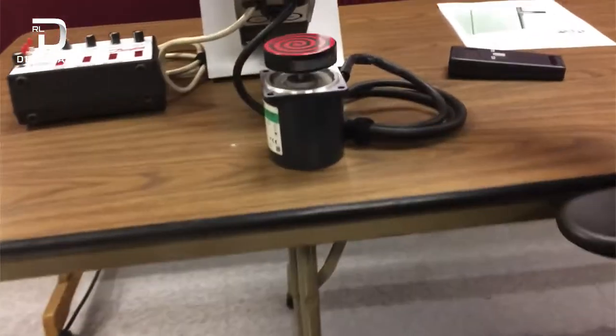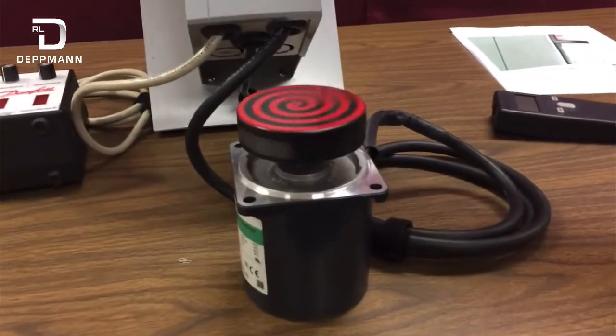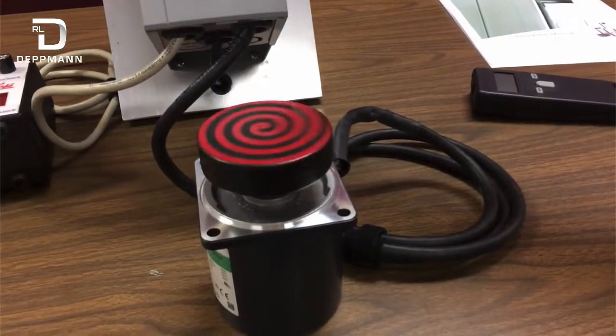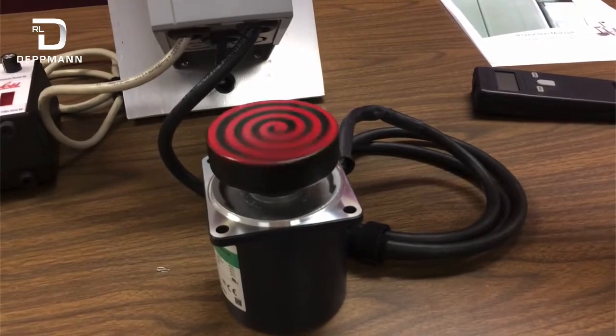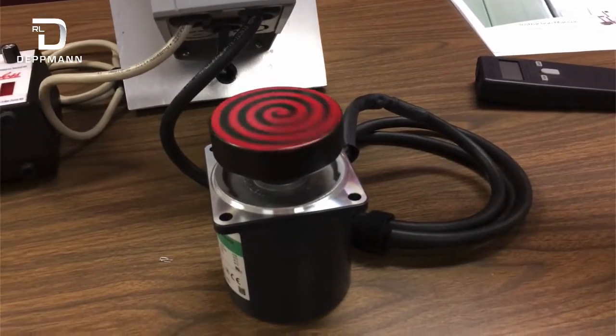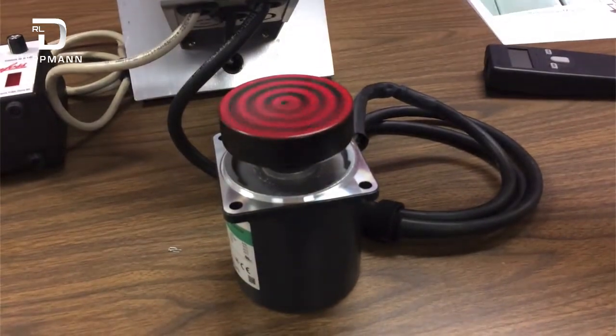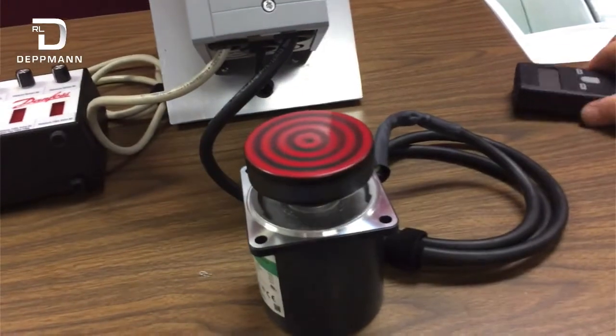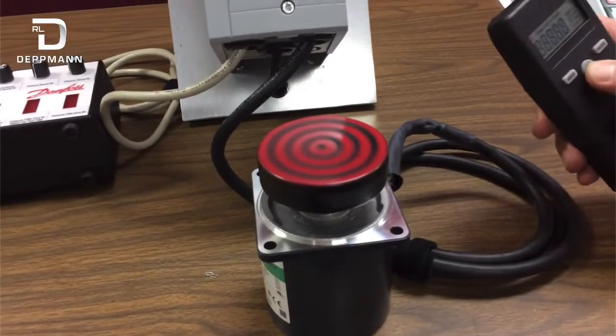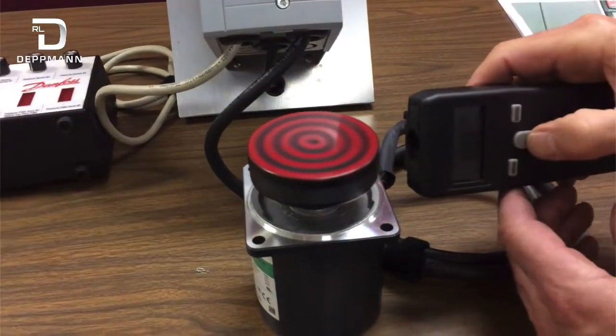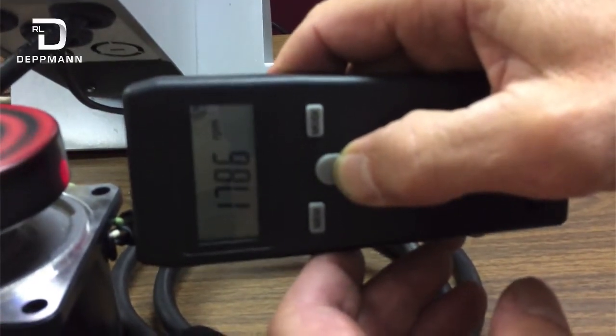Right now it's running at 18 Hz, our minimum speed. I'm going to boost that up and take it up to 60 Hz, which normally is our full speed upper limit. Now I have a tachometer here, and I'm going to hold it on there. At 60 Hz, it's running at 1786 RPM.